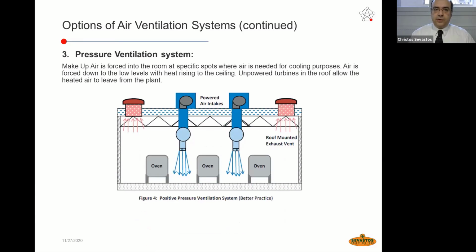The third option, which is a very good option, is the pressure ventilation system. Makeup air is forced into the room at specific spots, in the lower edges, not at the top of the ovens, but in the bottom, nearby the ovens. Air is forced down to the low levels with heat rising to the ceiling. Unpowered turbines in the roof allow the heated air to leave the plant. This is a positive pressure ventilation system in which, in comparison to the negative pressure ventilation system, we are applying air currents with rooftop units in which we are applying air supply covering the air demand of the burners for the ovens to operate efficiently.